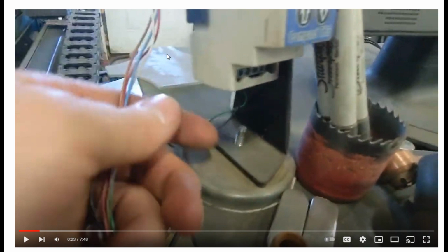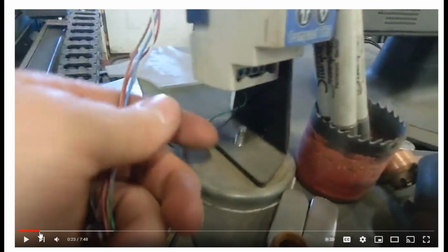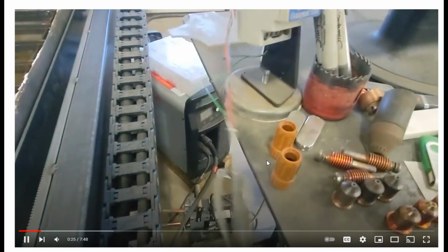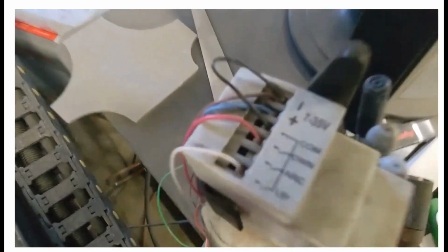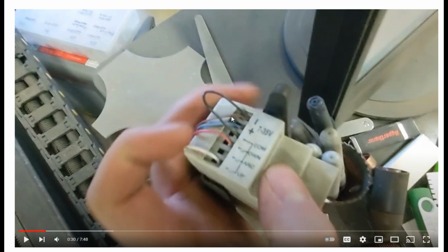We can see he's got his cable here. Of course, there's no grounds. It's not shielded. There's no drains. There's nothing. That dividing voltage comes up with gray wire on top. He's got a jumper from negative to common. He's also using daisy chaining, which you're not supposed to do. This is not best practice, mainly because if you have to troubleshoot, you could be chasing your tail.